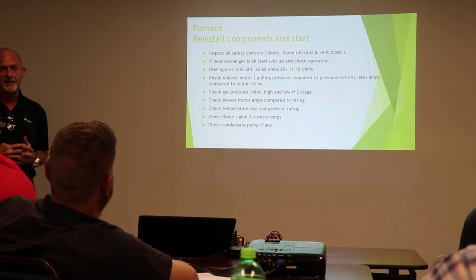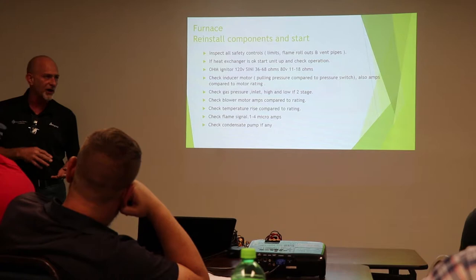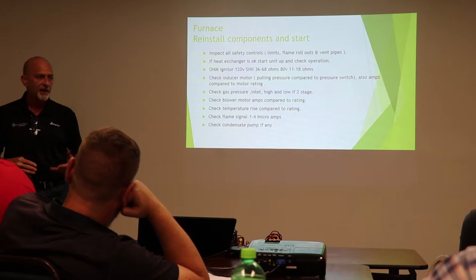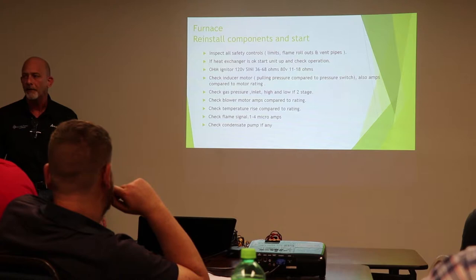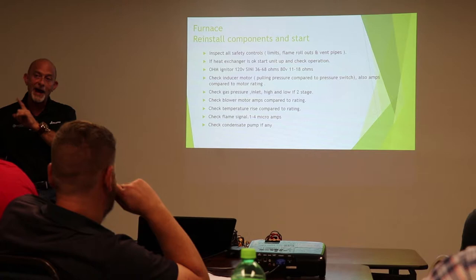Put it all back together. We want to light it off. We want to check all of our safety controls. We want to check our high limits, make sure they're working fine. Make sure our flame rollouts are fine. If you have a tripped flame rollout, what's that a sign of, guys, before you even take it apart? Most likely a cracked heat exchanger. Not always, though, on a 90-plus furnace.